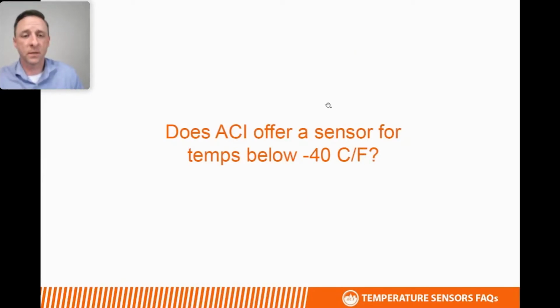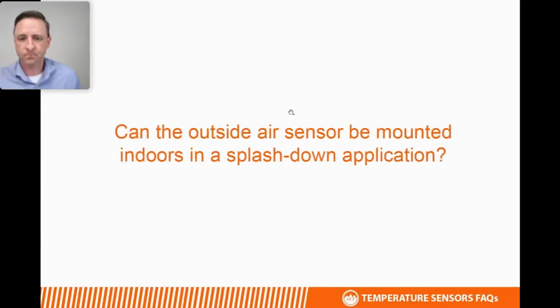Do we offer sensors for temperatures below -40 C or F? Yes, our standard thermistors are rated down to -40. We have a low temp option that I believe goes down to -192 degrees C. I have that in my cheat sheet here. I'm sorry, it's -198 degrees C that our low temp sensors can go down to. Those are RTDs or transmitters. Thermistors are not able to be accurate at that low of temperatures due to the nature of the sensing element. We mentioned this briefly before: outdoor air sensors used indoors. Absolutely, it's a great option that's low cost and weather tight for indoor applications where they might be wash down, splash down applications.